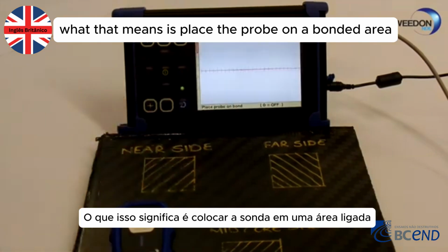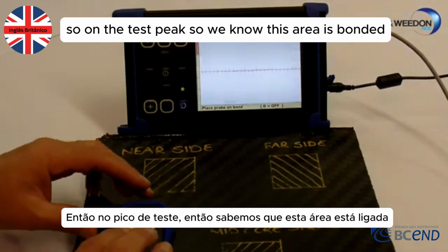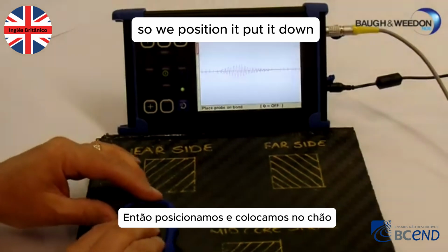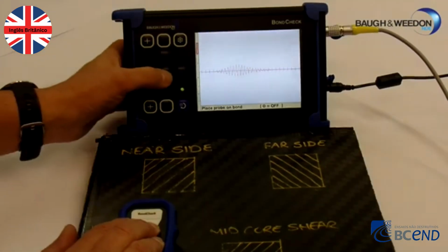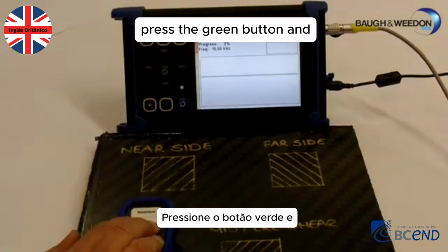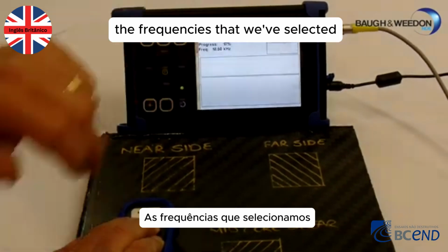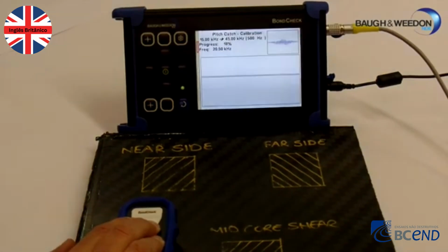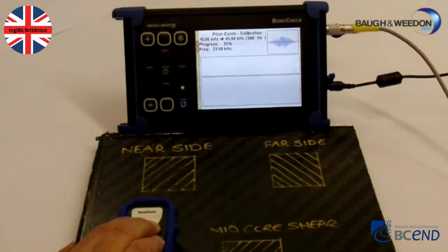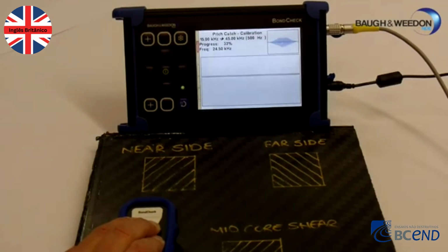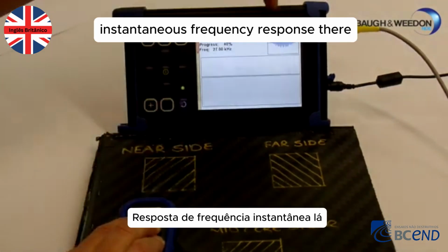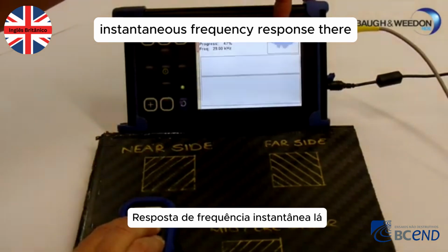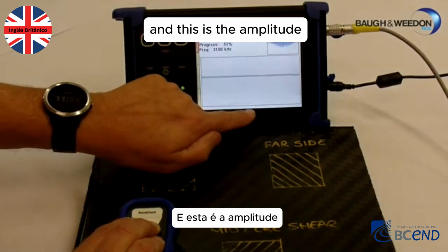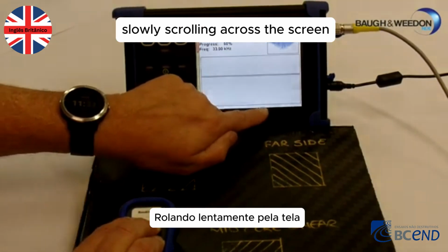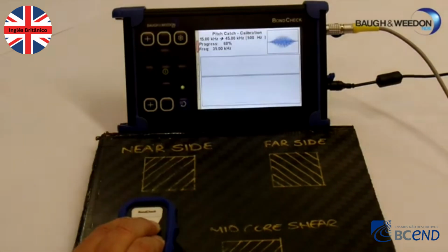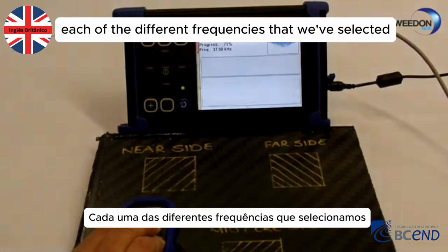And what that means is place the probe on a bonded area. So on the test piece, we know this area is bonded. So we position it, put it down, press the green button, and it'll now ramp through the frequencies that we've selected. It's the instantaneous frequency response there, and this is the amplitude slowly crawling across the screen as it goes through each of the different frequencies that we've selected.